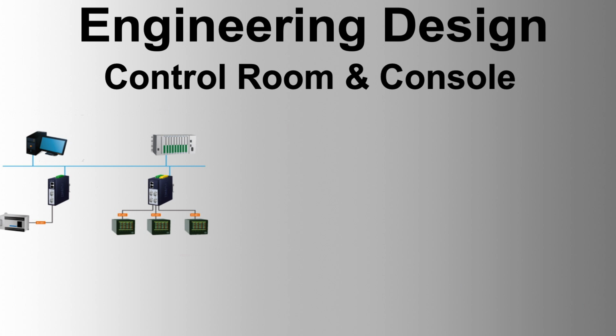Workstation configuration. The VDU with the most important process information should be positioned straight in front of the operator. Information on screens should be comparable in a horizontal direction. To improve the overview across several screens, workstations should be set up at angles of 10 degrees. The configuration should include sufficient writing space for the operator.